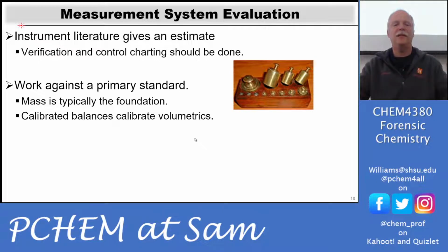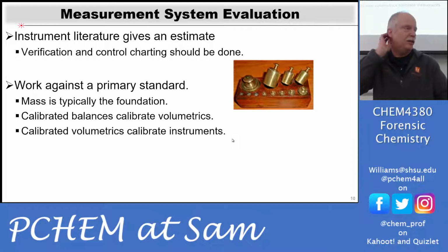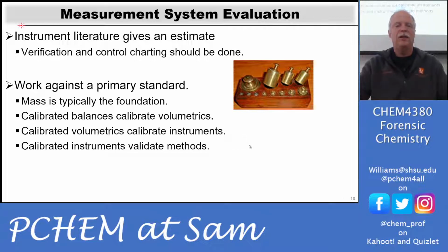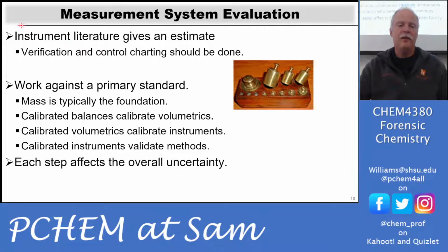And so those pipettes then are used to calibrate instruments, and those calibrated instruments will validate your methods. So every one of those steps affects the ones below it. It's pretty interesting that even our large instruments, GCMS, still stand on the shoulders of our lowly balance.